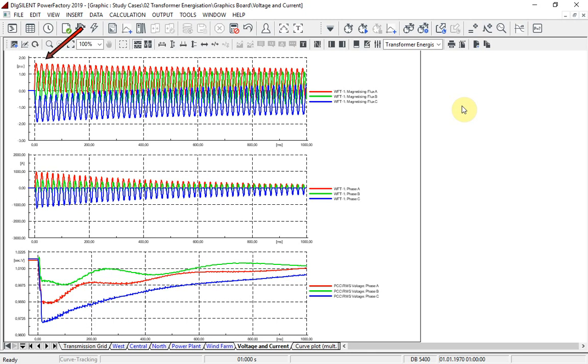Due to the non-linear flux-current relationship of the saturation curve, this will lead to high inrush currents, as shown here.